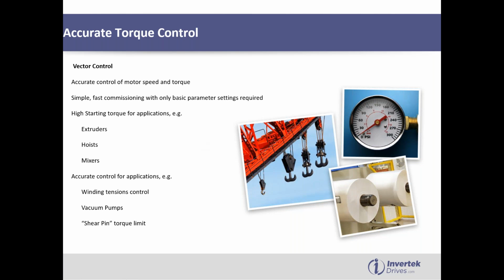We have very accurate torque control on the P2. In most applications where we're in speed control, but we need good breakaway torque to get the motor moving, to get the load moving, things like extruders or mixers or conveyors, or in hoisting applications where we need to hold the load against gravity. We have very, very good low speed torque availability on these drives.